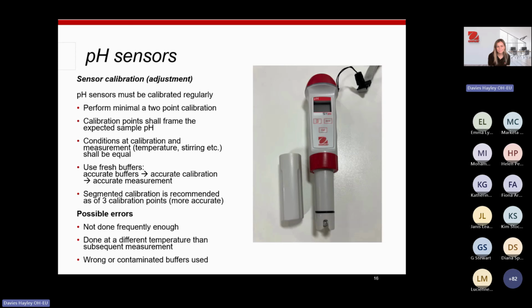Possible errors you will get if you are measuring your samples at different temperatures to those you calibrated at. That can cause potential differences, because, as we'll talk about later on, pH can be affected by the temperature of a solution. So always make sure that you're calibrating at the same temperature as you're measuring your solution. And you might get contaminated buffers or wrong buffers if you get any errors during calibration.